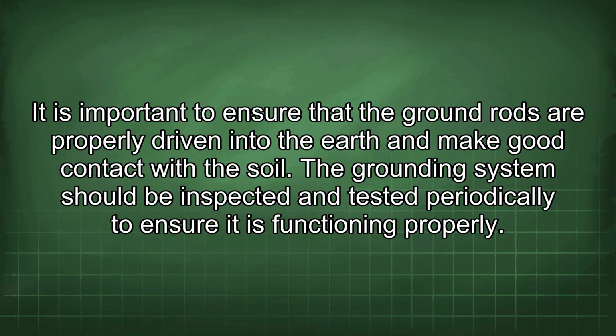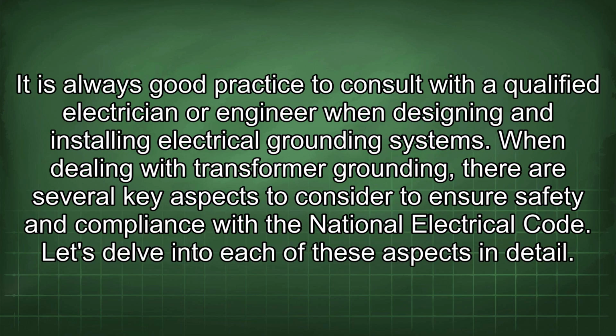It is important to ensure that the ground rods are properly driven into the earth and make good contact with the soil. The grounding system should be inspected and tested periodically to ensure it is functioning properly. It is always good practice to consult with a qualified electrician or engineer when designing and installing electrical grounding systems. When dealing with transformer grounding, there are several key aspects to consider to ensure safety and compliance with the National Electrical Code. Let's delve into each of these aspects in detail.